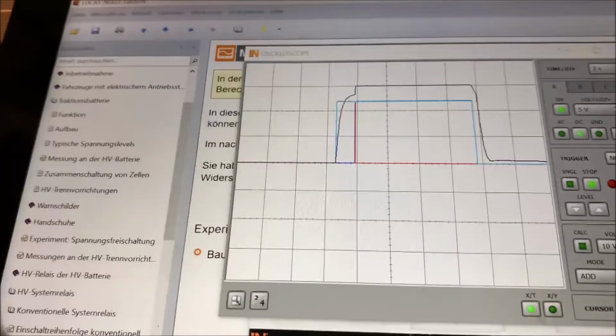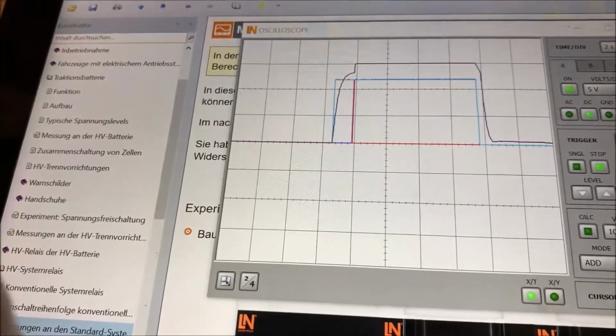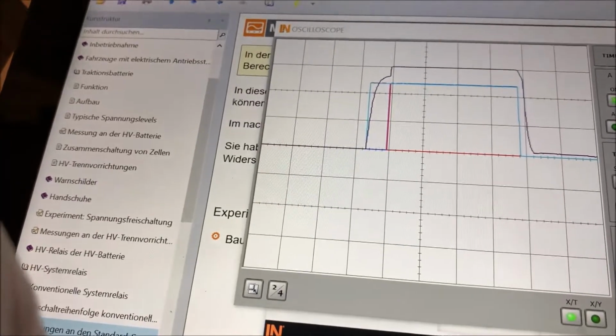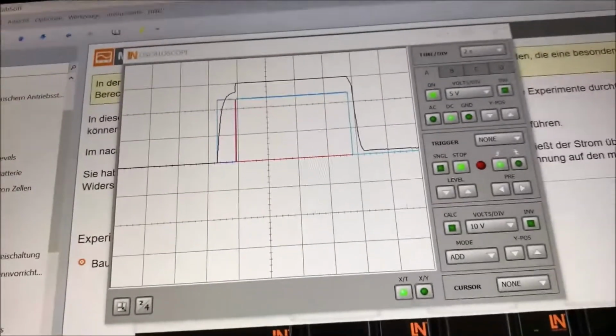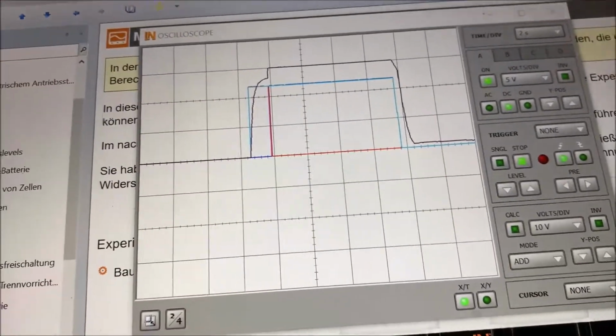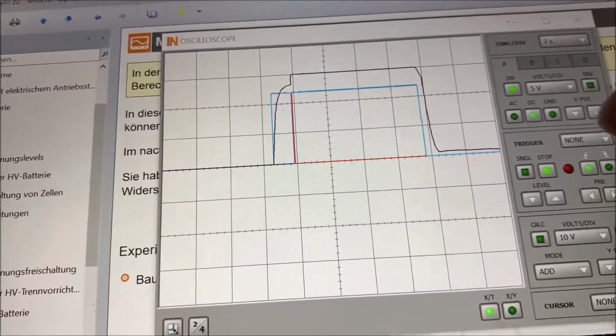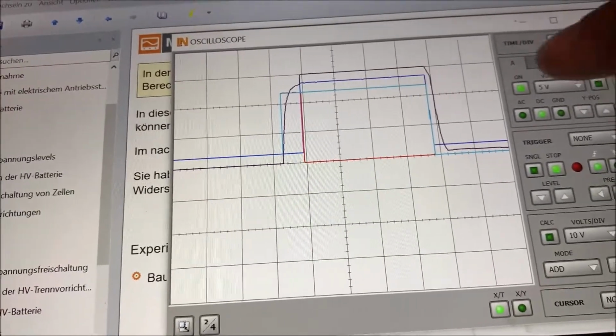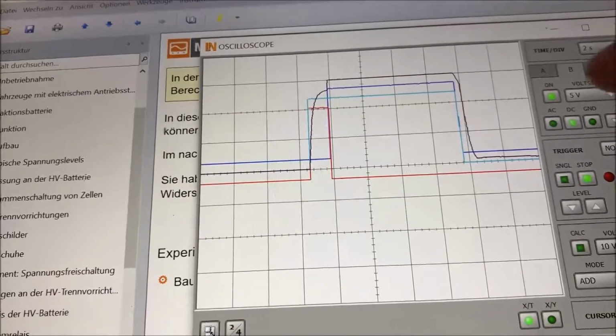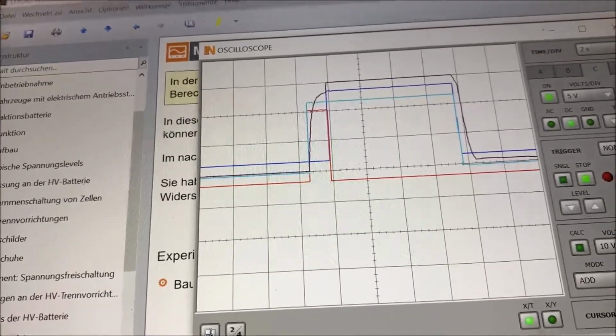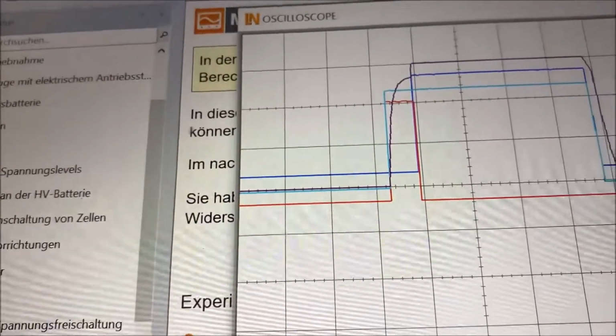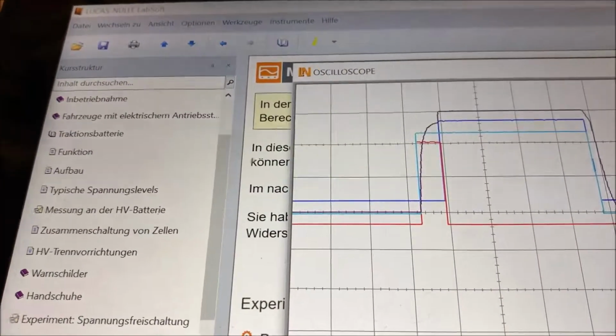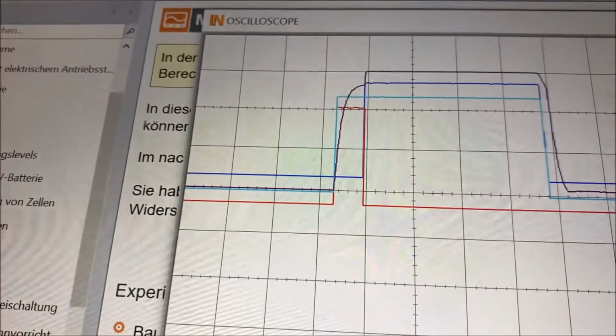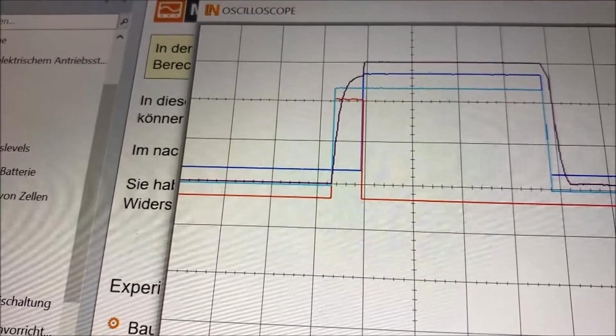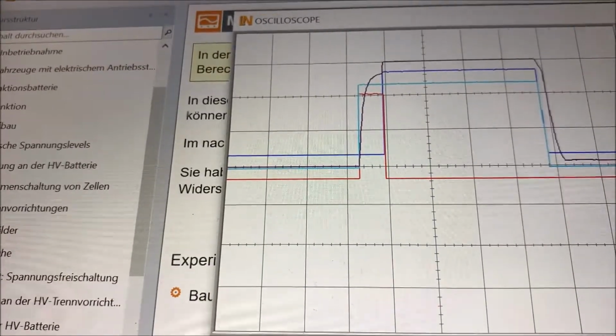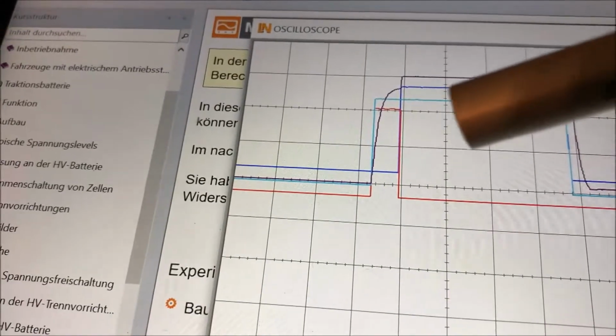Basically, right at the beginning you see that the high voltage minus relay is switching on and the pre-charging relay. I also can try to pull it a little bit out of each other. So let me check. When I go here, and when I go here, there you see now what basically happens. You see at first this light blue is the high voltage minus relay, that's switching on. Then we have the red, that's the pre-charge relay.